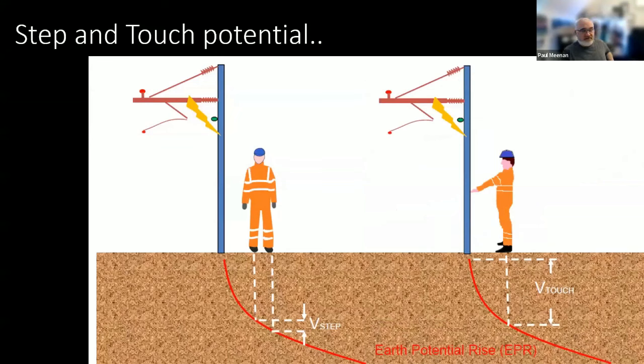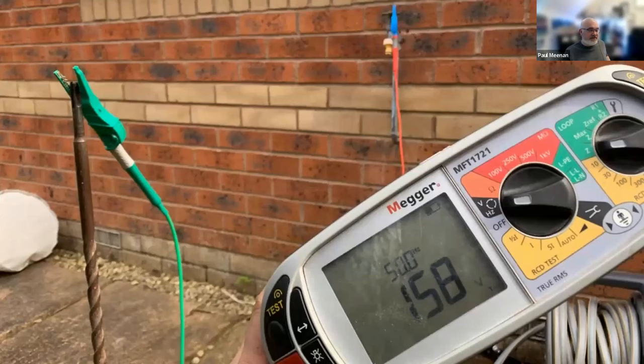On railways, we have some nice simple visuals on touch and step potential. We use PPE, we have insulated boots, we have rubber matting in switch rooms, all sorts of stuff to protect us. This is my favorite picture. It was taken at a domestic property, and it shows a broken neutral on the supply, 158 volts, and the clip is attached to the outside water tap, which people plug their hose into. The electrician just put a drill into the ground and measured 158 volts. So that proves the concept that voltages grade across the ground. They can be a hazard because I could touch that drill bit and also the tap and get an electric shock. So just be careful when you are configuring your earthing and bonding.